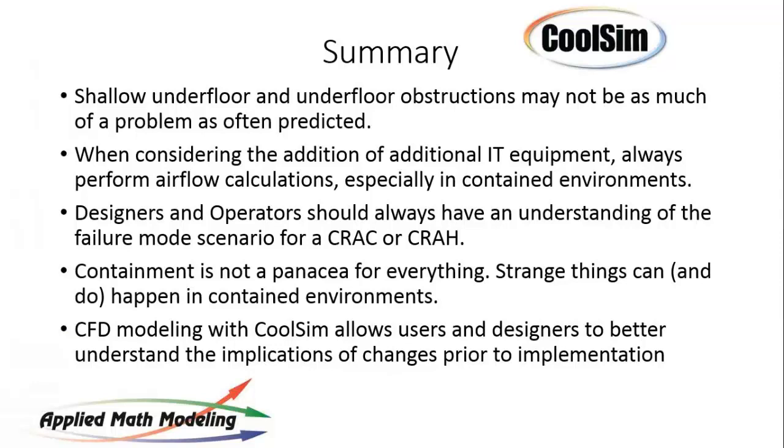Then the operators could use it to do simulations if a new customer came in to see how the rooms would behave, and also do failure analysis by turning off each CRAC unit one by one once additional load would be placed, to understand how their reaction and escalation procedure needed to be modified to fit the load.